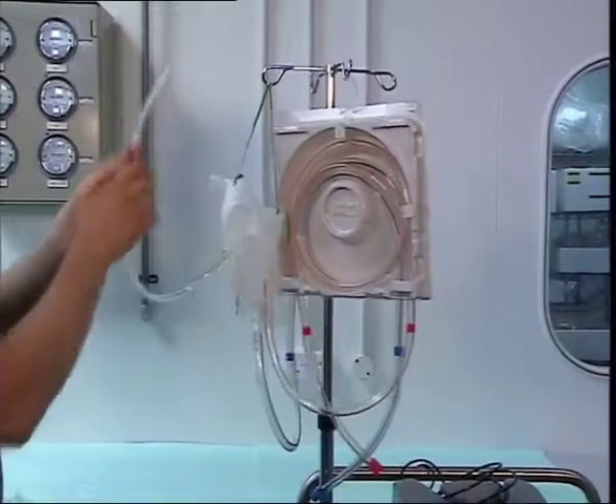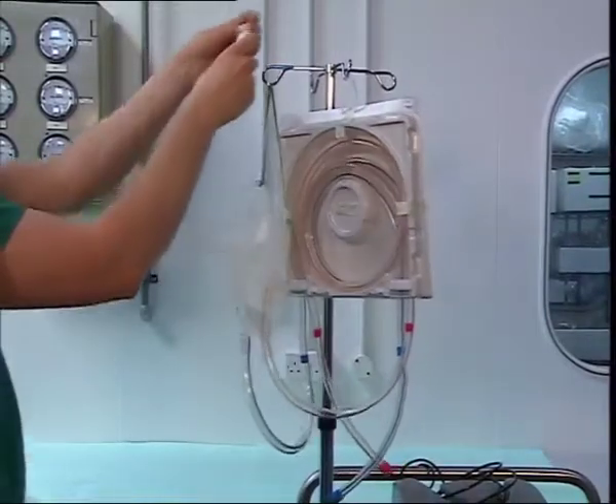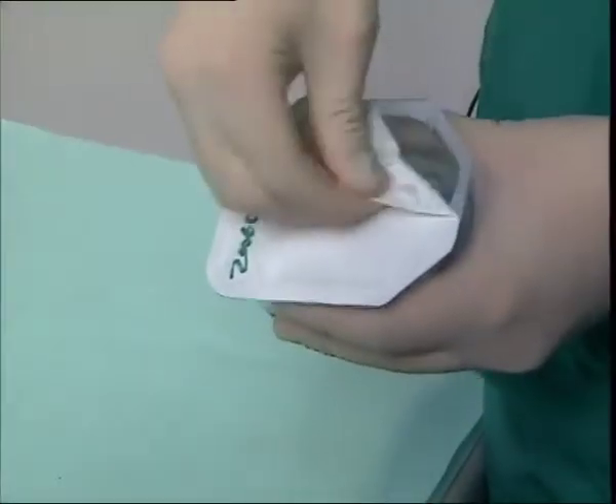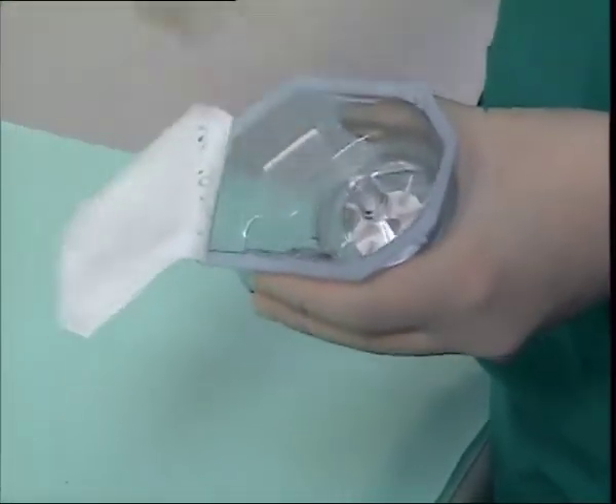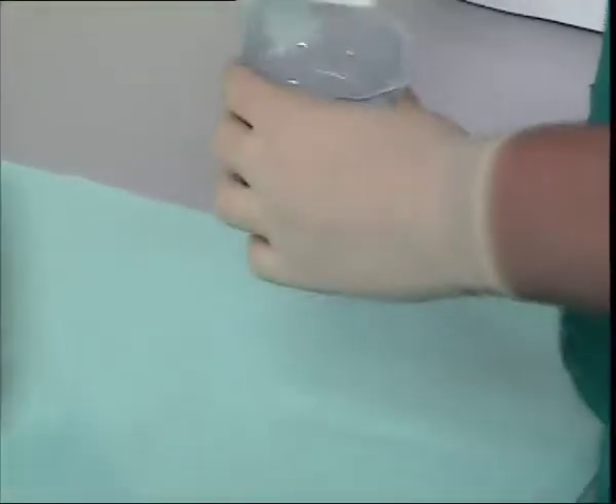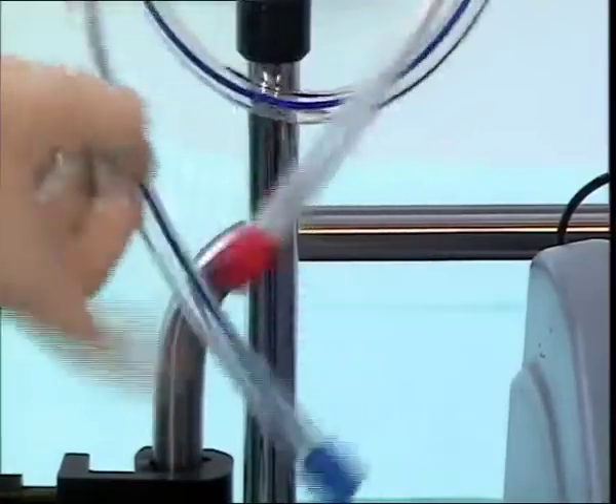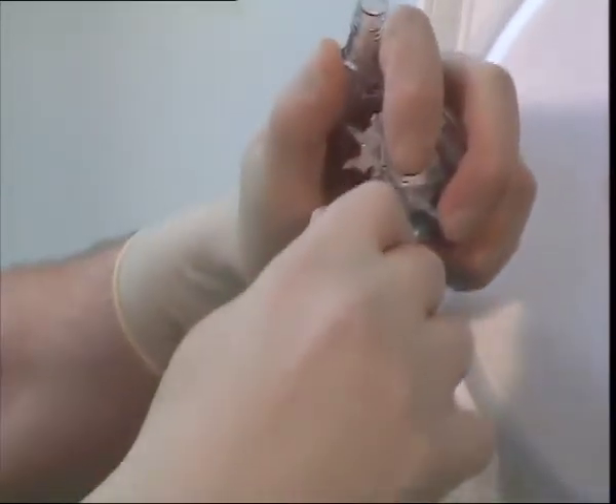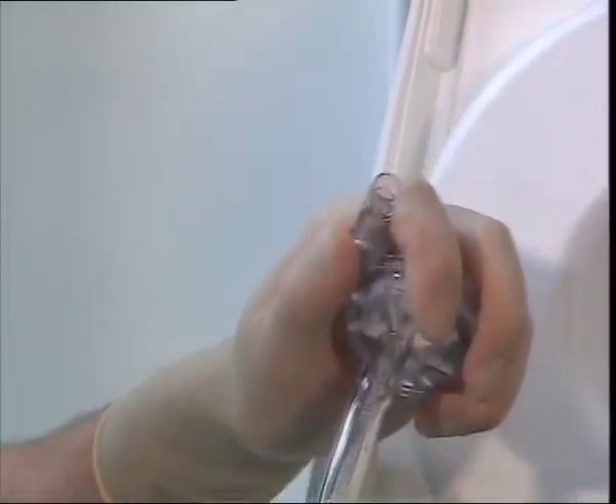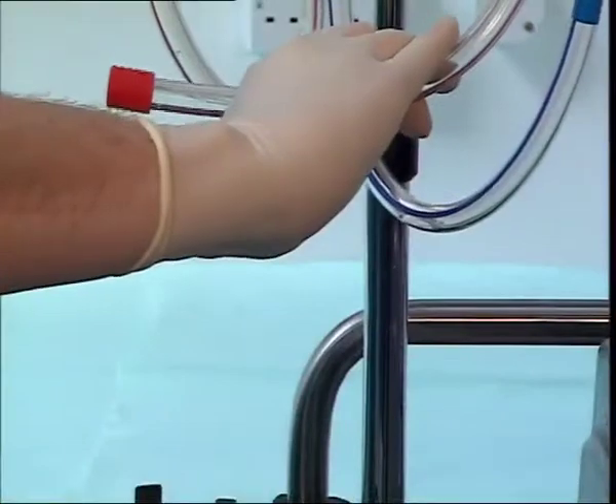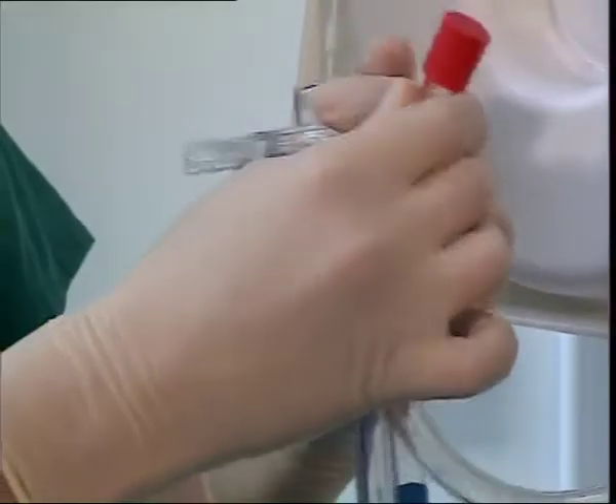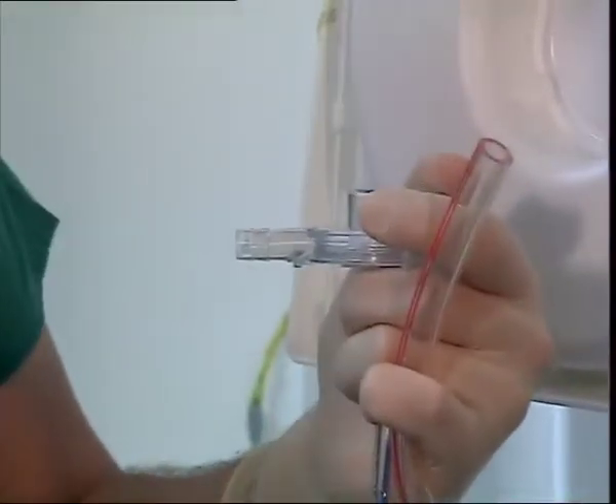Hang the priming circuit on the drip stand. Be sure to wear sterile gloves when opening the pump head inner packaging. Using standard aseptic technique, attach the blue tubing to the connector marked inlet and the red tubing to the outlet of the pump.